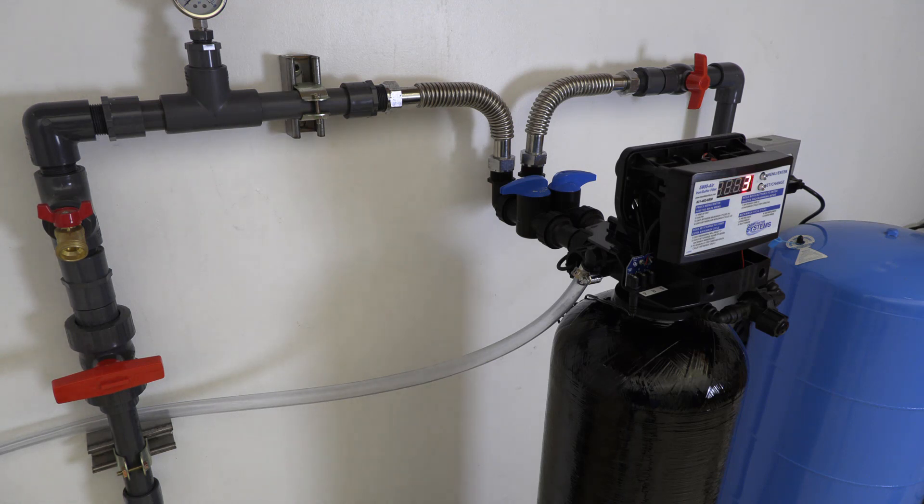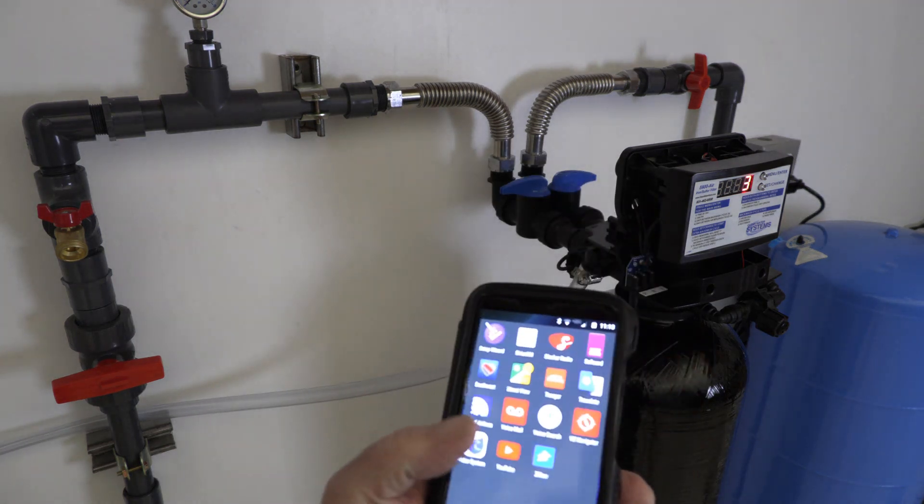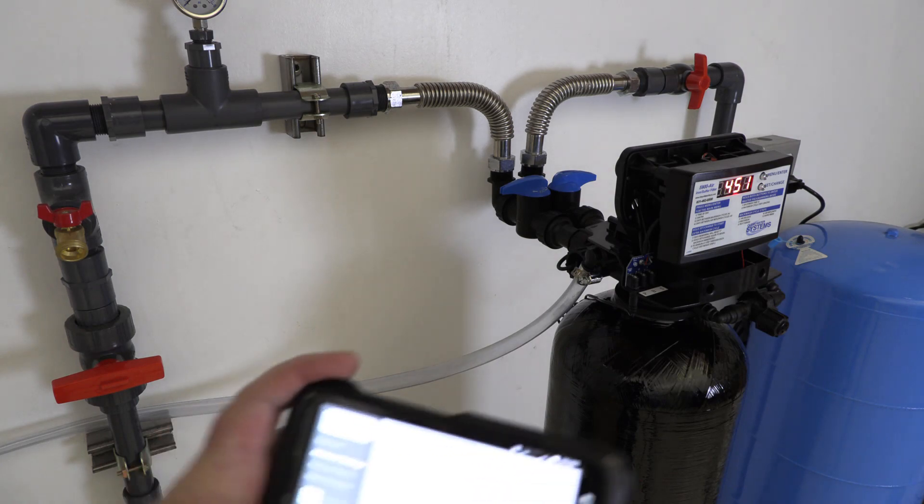For the first one, we want to use the backwash cycle, cycle number two, and the rapid rinse cycle, cycle number five. We'll skip both the rest period and cycle four air replenish. So I'm going to go ahead and do this using the Bluetooth.